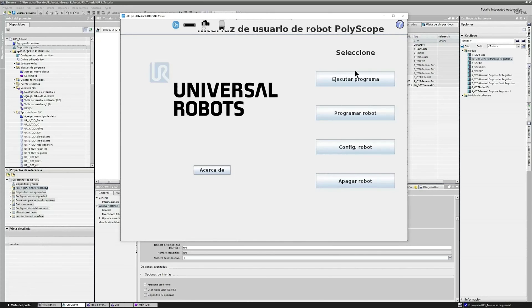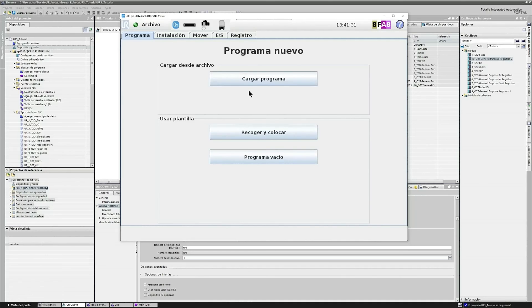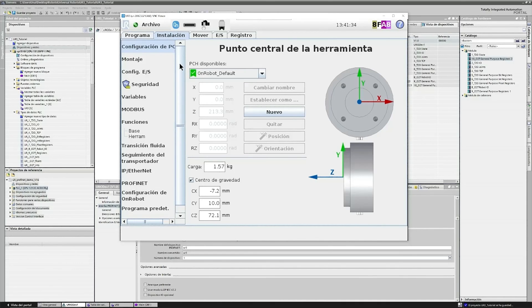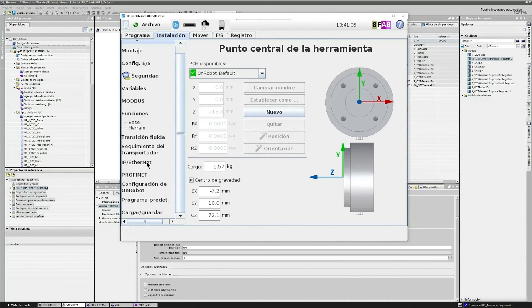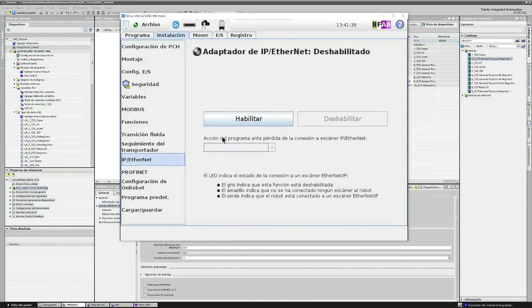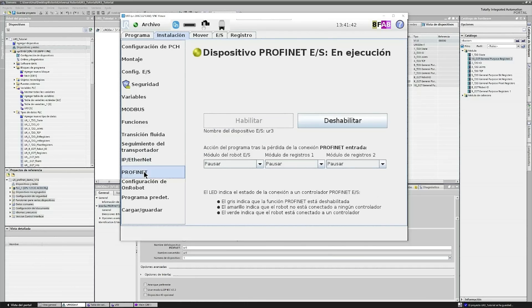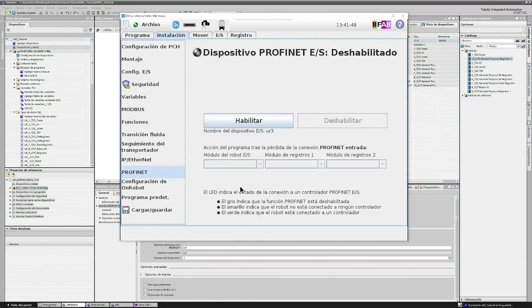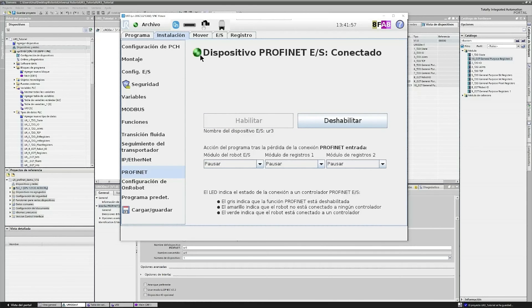Once we establish the IP address and confirm there is a connection, we go to program the robot. Here in installation, we go into Profinet. First, we check that we don't have other problems with other types of networks like Ethernet IP, and we enable Profinet. In our case, Profinet is running, so I disable it and then enable it again.